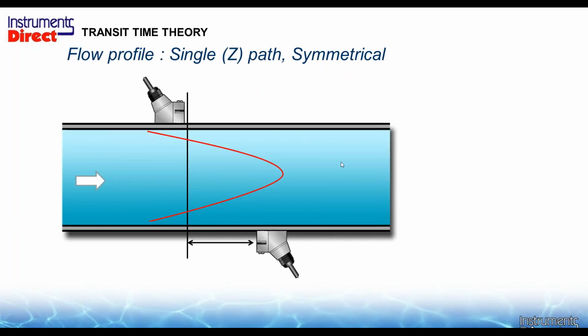So let's look inside the pipe here. We have a picture of the 2 sensors, one on each side of the pipe. We have our perfect flow parabola here, so our Reynolds number is perfect. It's fastest in the center, slowest near the pipe wall. We don't care how blunt it is. That's a function of what the flow rates are. Flow is going from left to right. So I program my meter, and then the flow meter will tell me that this sensor goes here, and this sensor has this spacing. And if I put them in this particular application, bing, I send a sound beam from one sensor to the other, line of sight, straight as an arrow, and I get my signal there. We now have an optimum performing ultrasonic flow meter because the math is correct.